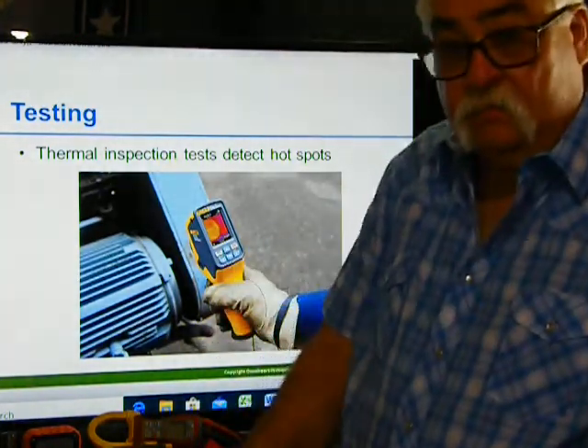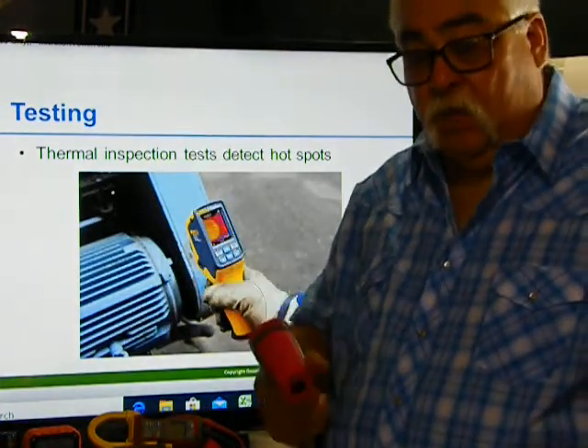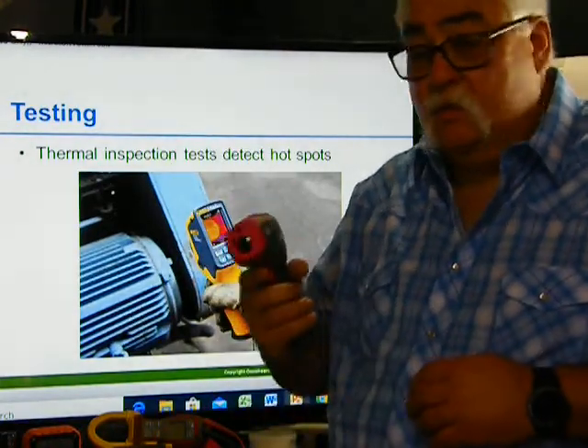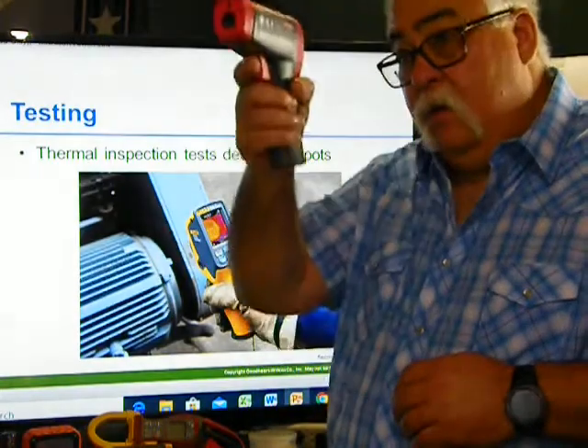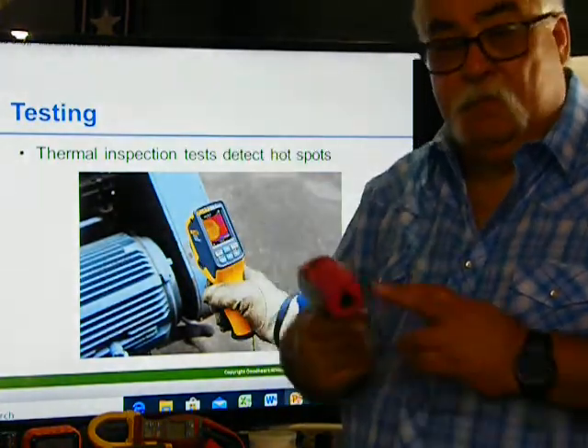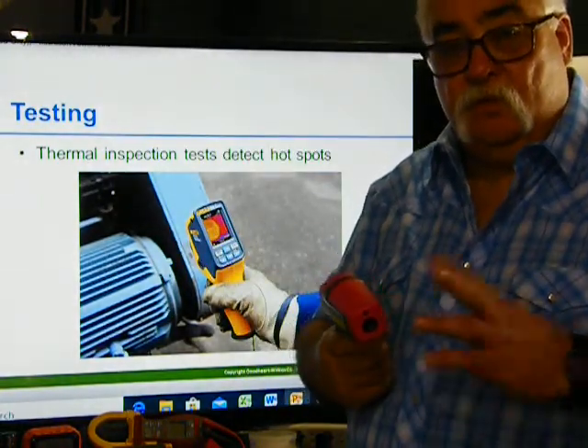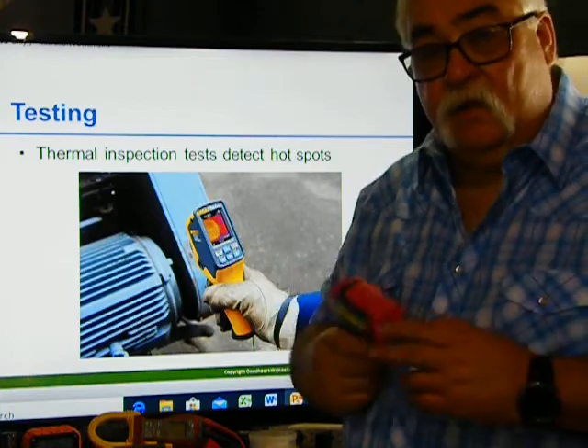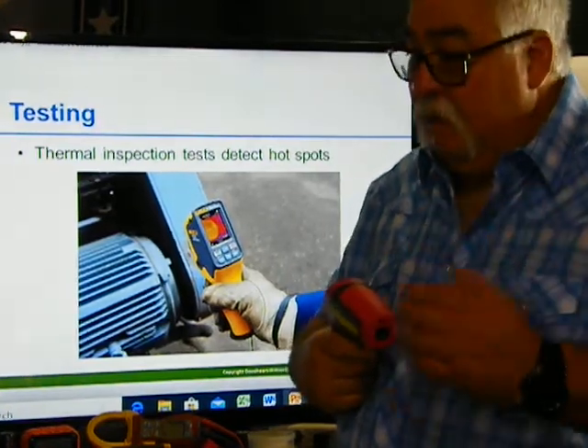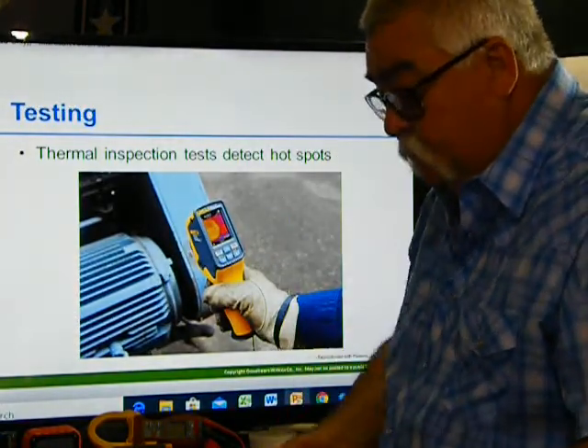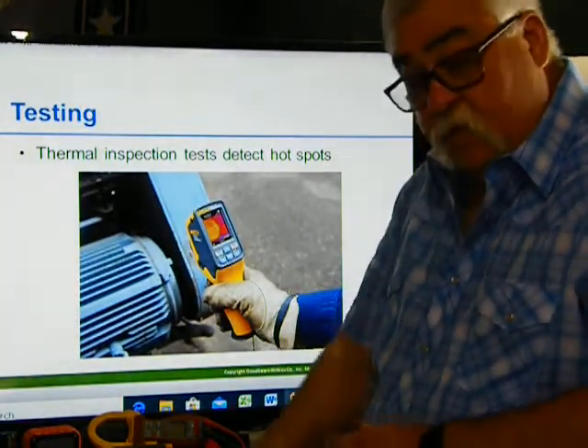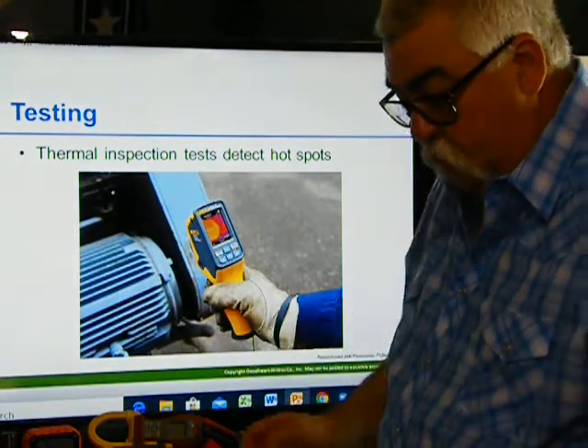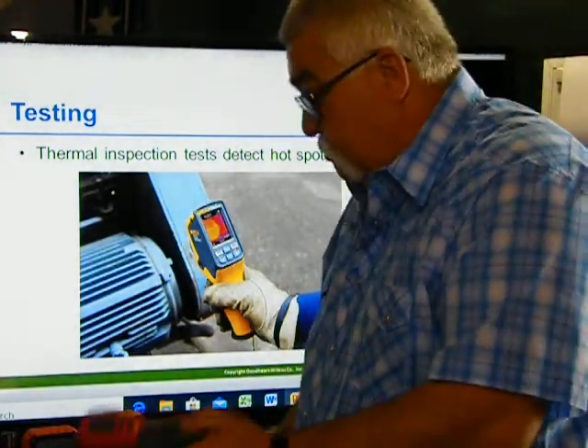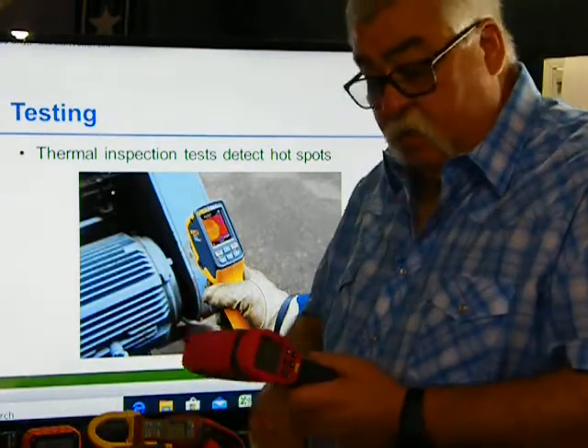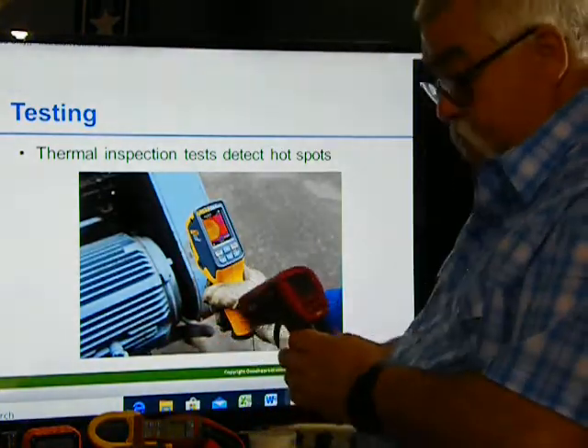So going back, transformer. Okay, you get a panel. You know, you can use one of these. You get a panel, open the panel up. Wherever your bolt's at, check it to make sure what the temperature is. And as long as you're around 86 degrees, you're fine. If you're above that, what's causing it? So you have to be careful with it. It's always nice to do the thermal, you know, checking motors, checking transformers so they're not hot, switchgear.